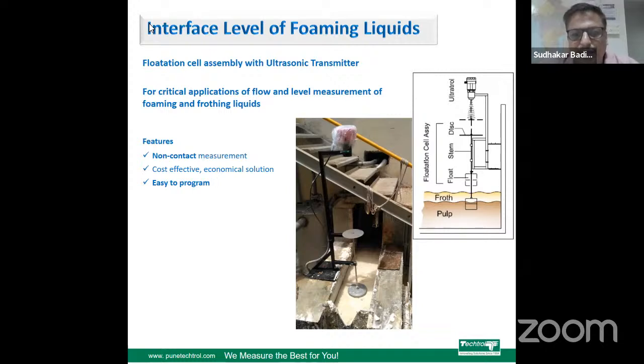The float is actually floating with the liquid level, which is under the foam. The liquid is under the foam. So it is designed for the liquid specific gravity. So it is not detecting the foam.